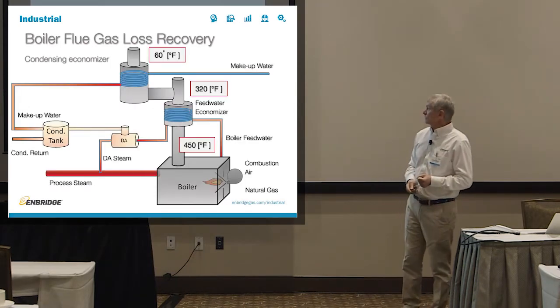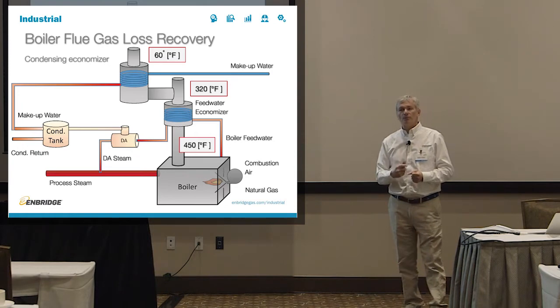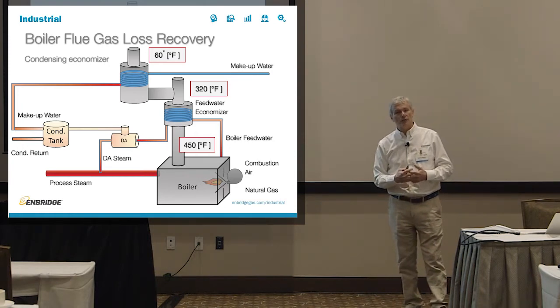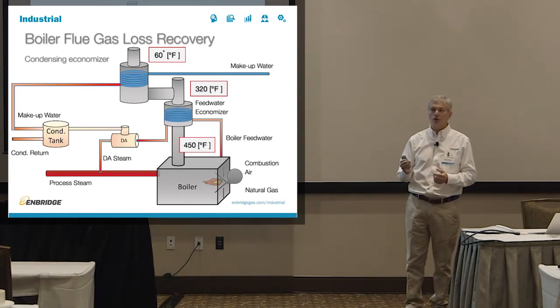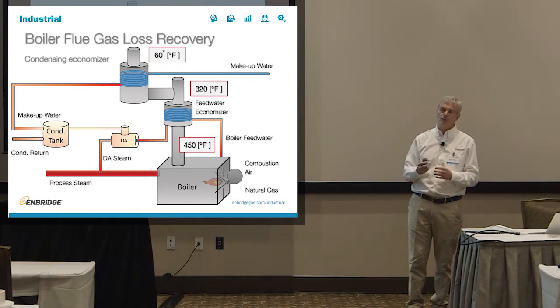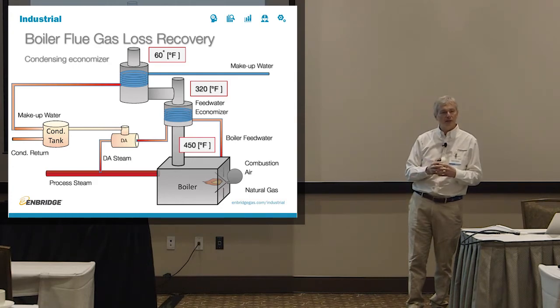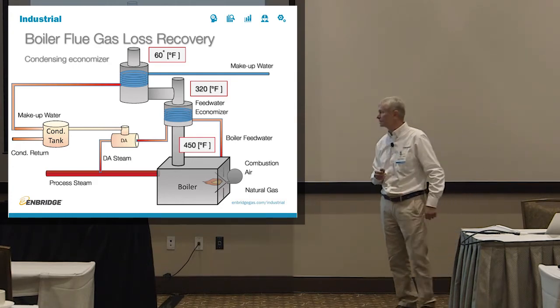Condensing economizer, of course, you can put on top of the feed water economizer. If you already have a feed water economizer, you can put a condensing economizer after it, because the feed water economizer, as we said, leaves a lot of heat, and it hasn't recovered any of the latent heat. So all the moisture in the flue gas stream is still available to harvest.